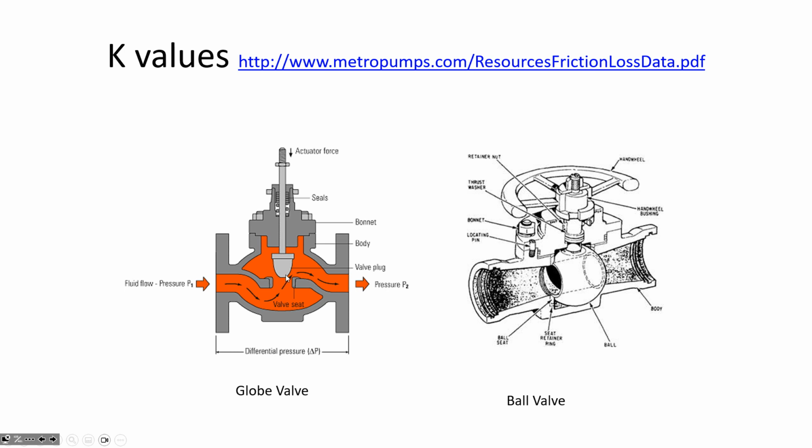The opening is donut shaped around this plug that normally would fit down into the valve opening if it's closed. When you pull it up out of the way, there's just a ring of opening that the water's having to flow through. And so it's really contracted. Even when the globe valve is all the way open, there's a contraction inside of this fitting. And that contraction is taking a lot of energy out. The water is losing energy as it flows through. It reestablishes its outgoing flow direction, but it's changed direction several times as it goes from entrance to outlet.